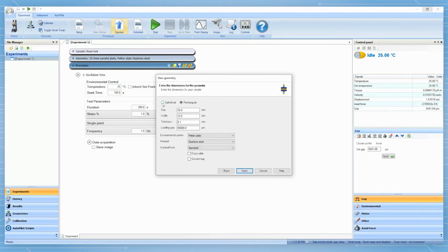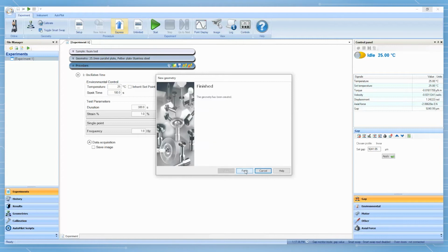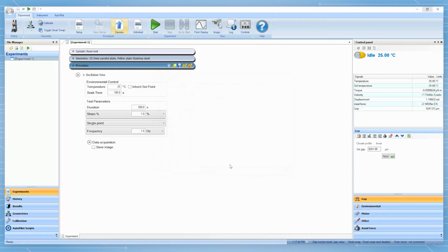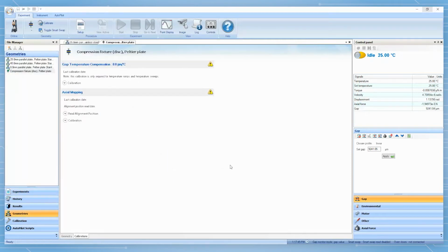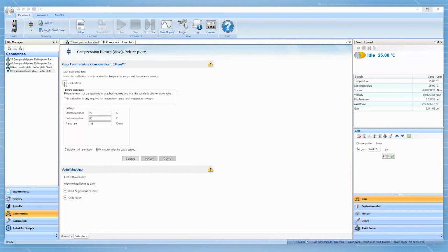Choose the correct sample dimension, for example cylindrical, and the correct temperature control system. Follow the procedure to finish creating this geometry file. Then Trios will lead you to perform the geometry calibration. For geometry gap temperature compensation calibration, the operator needs to select the same temperature range and same heating rate as it is required for testing the sample. However, if the compression measurement is conducted at an isothermal temperature, then this calibration step is not needed.